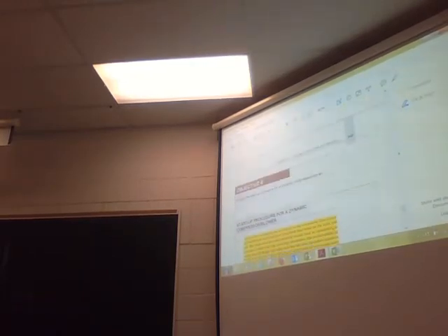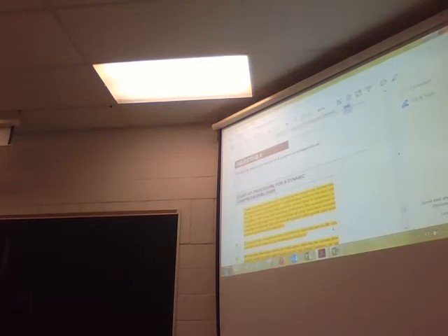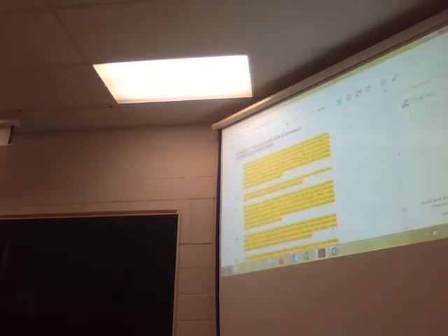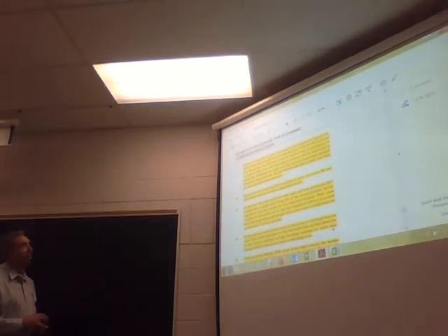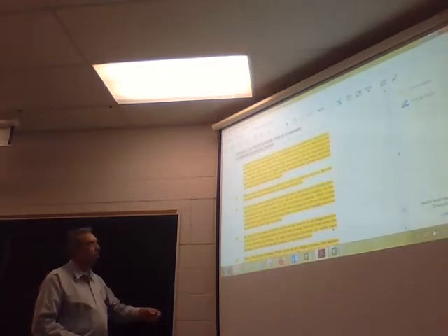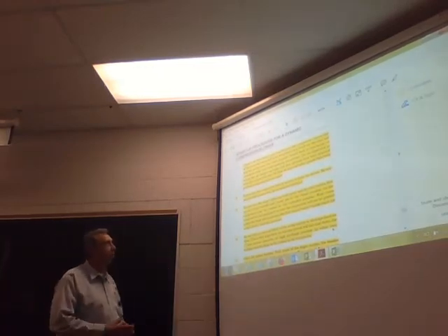All right. Startup procedure for a dynamic compressor. You should read through that to get all the details of the compressor. Check to be sure that no one is working on the compressor again. It's a good idea. Ensure that the compressor lube oil system is ready for service. Be sure the lube oil reservoir has an adequate level in it.